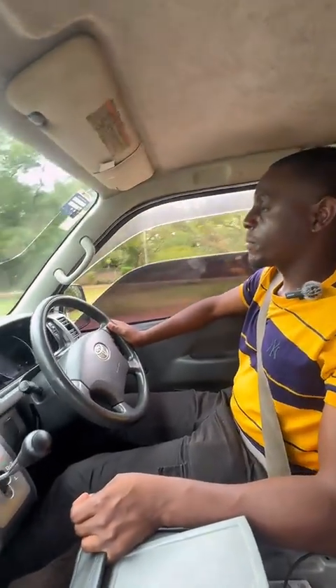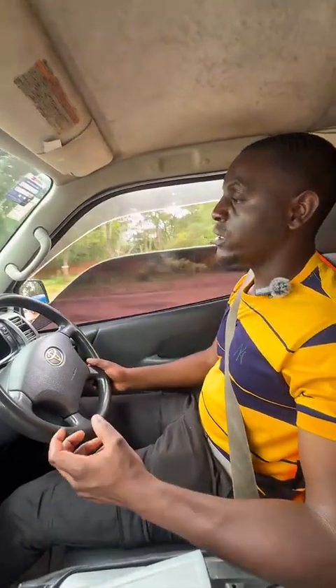Right, so today, tonight, fault diagnostics or fault diagnosis for an 8 kVA Deye solar system, coupled with a 10 kilowatt battery and 18 solar panels. This client reached out to us on Facebook and told us that whenever the system is in battery mode, it's tripping when an iron or a microwave is connected on the 8 kilowatt system. But I know for a fact that an iron or microwave can run smoothly on an 8 kVA Deye inverter, so there must be a problem.